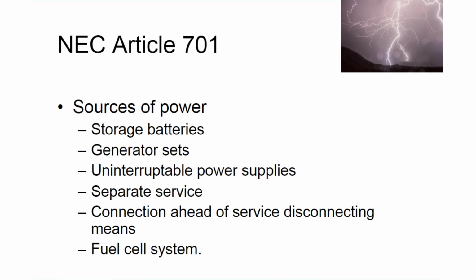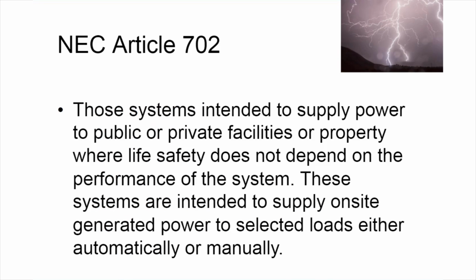The codes are fairly consistent with what qualifies for an emergency source. It could be storage batteries, generator sets, UPSs, separate services in specific occasions, connection ahead of a service disconnect, again, not always, but in certain occasions, and fuel cell systems. You might also look at local codes and ordinances because for healthcare, all of these don't always apply. Typically, most healthcare occupancies require diesel generators. And then quickly, Article 702, which covers optional standby systems. Some examples of what might be covered by this article are HVAC systems or data systems that are not required for life safety.